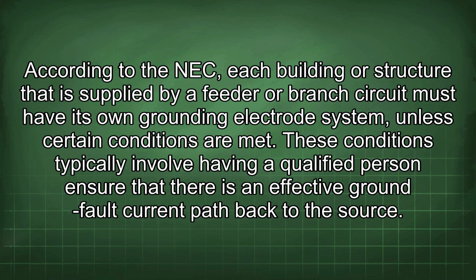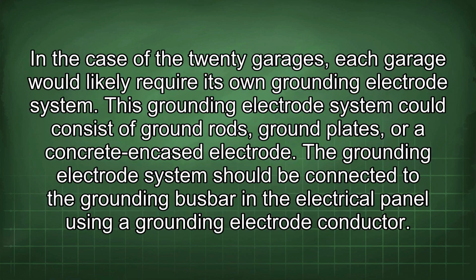According to the NEC, each building or structure that is supplied by a feeder or branch circuit must have its own grounding electrode system unless certain conditions are met. These conditions typically involve having a qualified person ensure that there is an effective ground fault current path back to the source. In the case of the 20 garages, each garage would likely require its own grounding electrode system. This grounding electrode system could consist of ground rods, ground plates, or a concrete encased electrode.